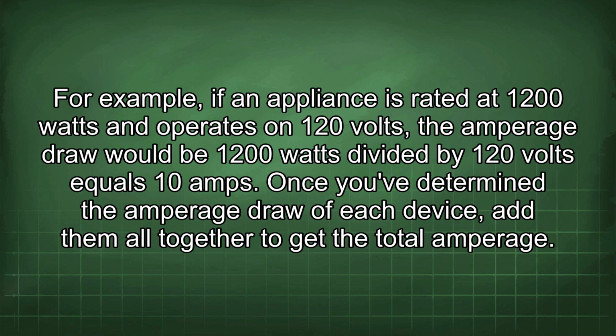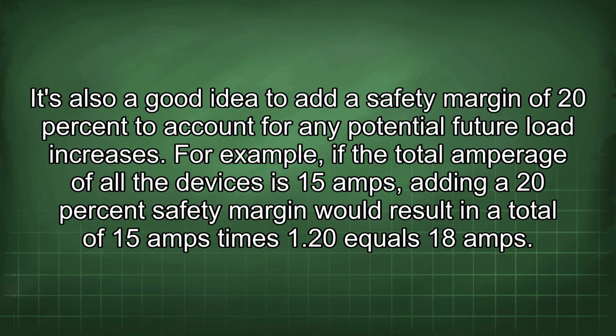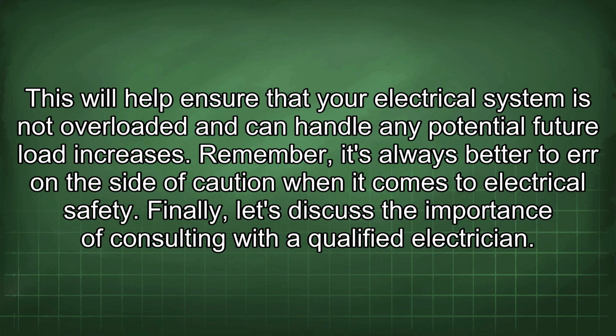Once you've determined the amperage draw of each device, add them all together to get the total amperage. It's also a good idea to add a safety margin of 20% to account for any potential future load increases. For example, if the total amperage of all the devices is 15 amps, adding a 20% safety margin would result in a total of 15 amps times 1.20 equals 18 amps. This will help ensure that your electrical system is not overloaded and can handle any potential future load increases. Remember, it's always better to err on the side of caution when it comes to electrical safety.